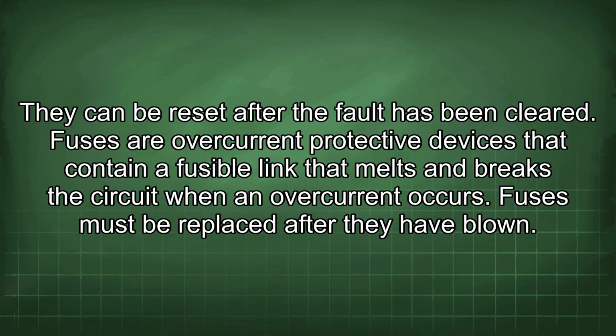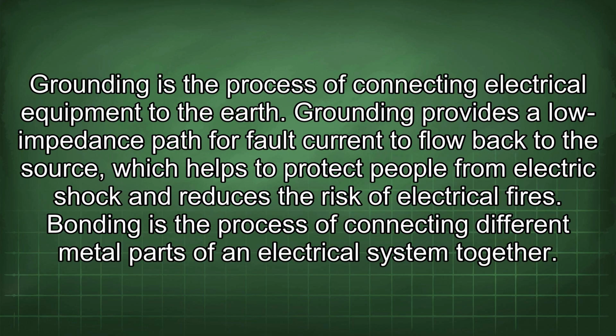Fuses are overcurrent protective devices that contain a fusible link that melts and breaks the circuit when an overcurrent occurs. Fuses must be replaced after they have blown. Grounding is the process of connecting electrical equipment to the earth. Grounding provides a low impedance path for fault current to flow back to the source, which helps to protect people from electric shock and reduces the risk of electrical fires.